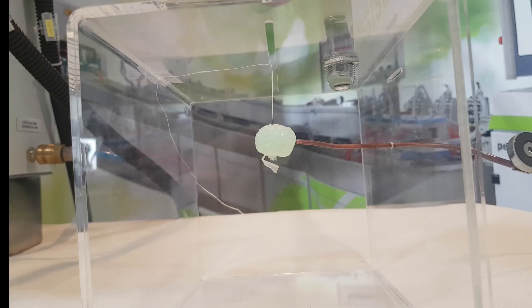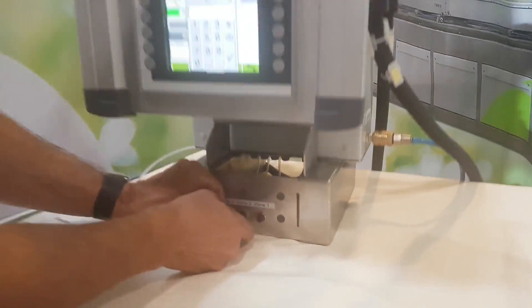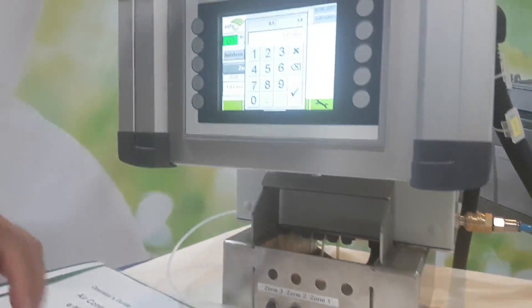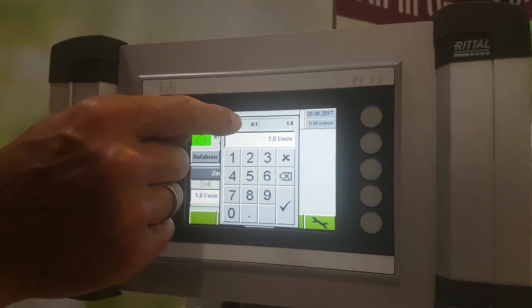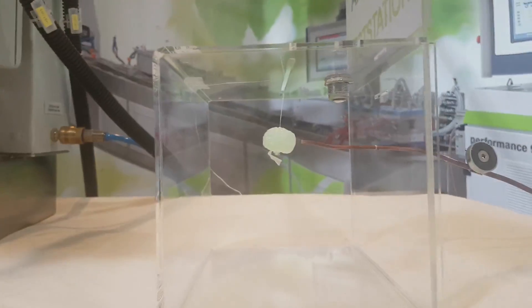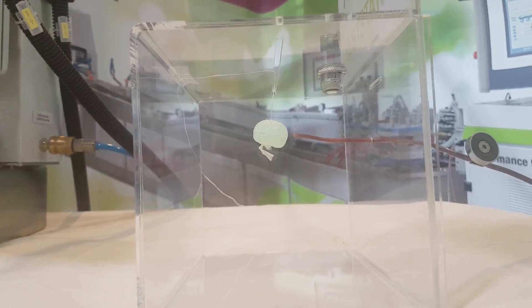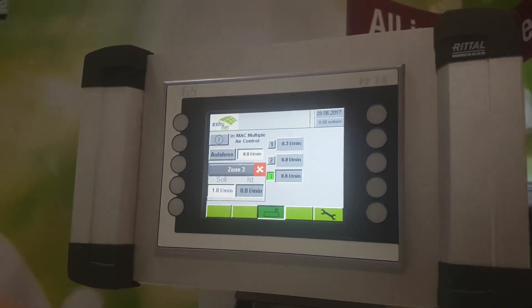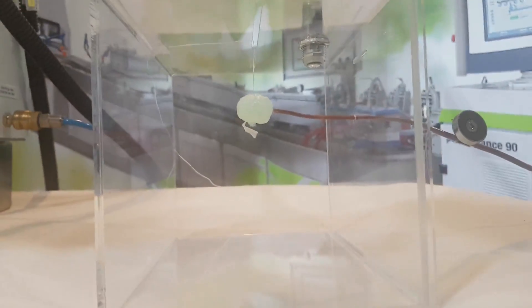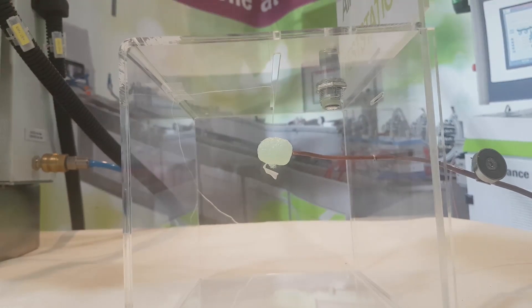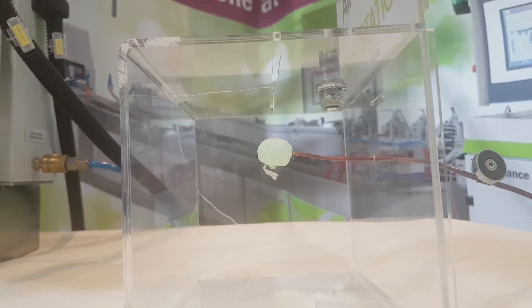Now I switch from zone 2 to zone 3. Zone 3 is that zone with the smallest range we can adjust. So it is from 0.1 to 1 liter per minute. So when we go back now, we have some vibrations. We switch it off first. Then we check the foam piece and wait until there is no movement anymore or quite no movement.